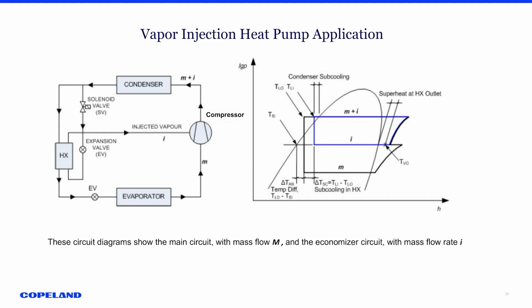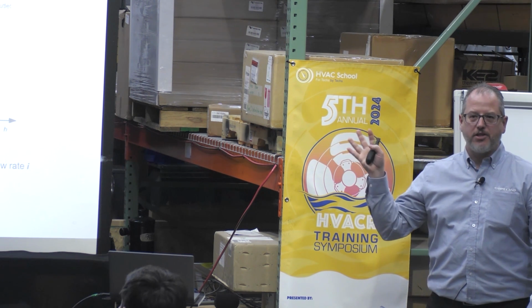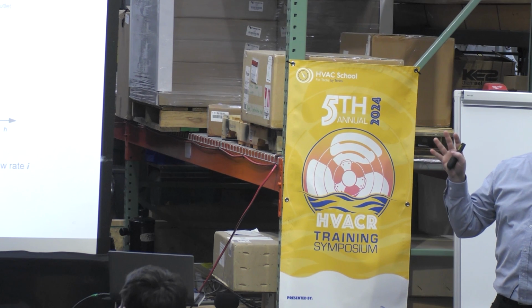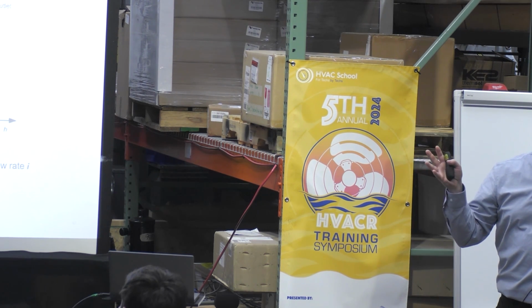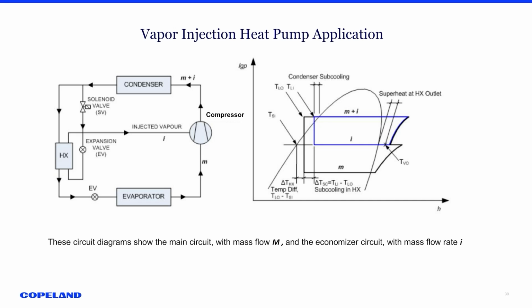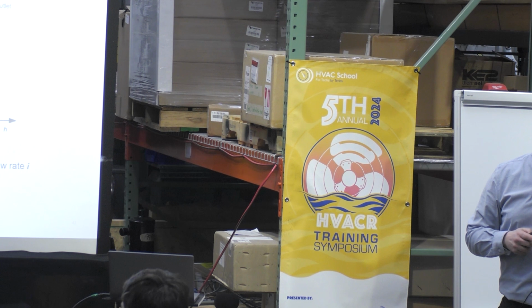So this is a pressure enthalpy diagram. With vapor injection, the thing we're adding here is a heat exchanger, okay? So we have an extra load that we're adding, but with this vapor injection system, we get 50% more capacity and 20% more efficiency. Okay, so ultimately now I can use a smaller compressor, because it's so much more efficient. And with this heat exchanger, I'm subcooling that liquid going into my expansion valve, okay?